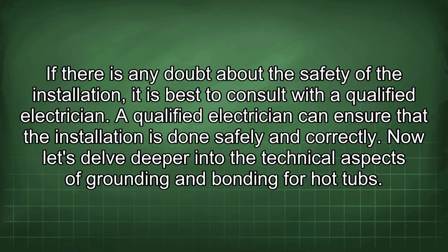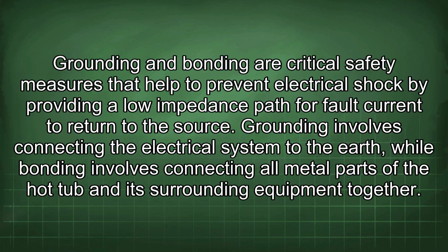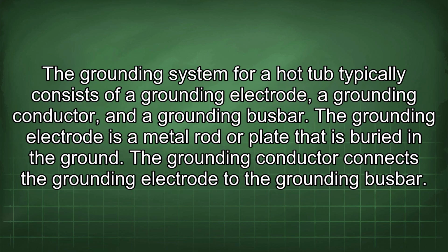Now let's delve deeper into the technical aspects of grounding and bonding for hot tubs. Grounding and bonding are critical safety measures that help to prevent electrical shock by providing a low impedance path for fault current to return to the source. Grounding involves connecting the electrical system to the earth, while bonding involves connecting all metal parts of the hot tub and its surrounding equipment together. The grounding system for a hot tub typically consists of a grounding electrode, a grounding conductor, and a grounding bus bar. The grounding electrode is a metal rod or plate that is buried in the ground. The grounding conductor connects the grounding electrode to the grounding bus bar.